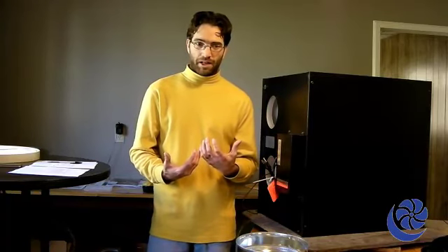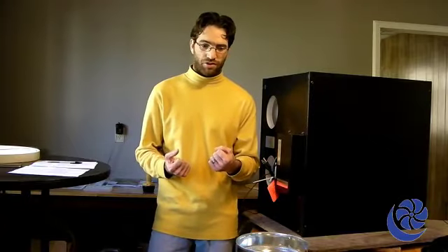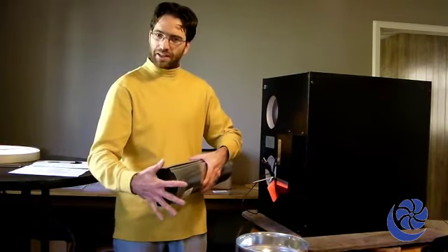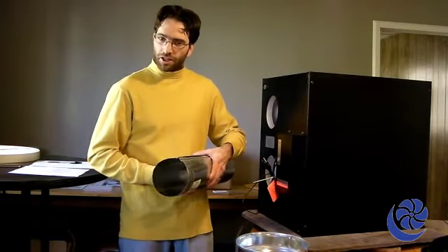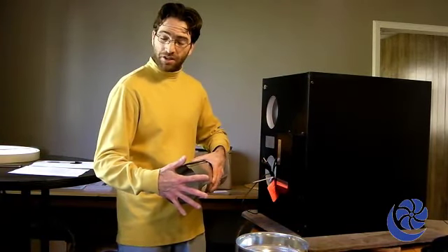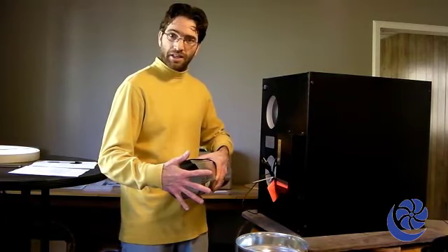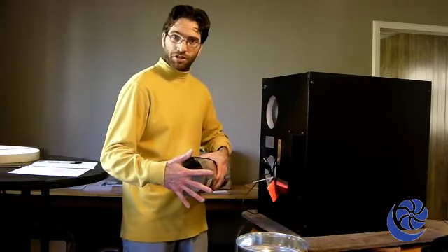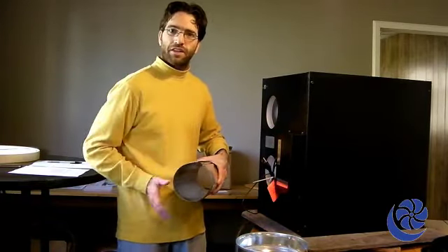Combine that with keeping in mind that we are delivering a very highly filtered airstream, meaning that we are pushing this air through a very dense filter, which also costs electrical money to force air through a filter. If I were forcing air through this duct without anything blocking it, and I were moving 100 cubic feet per minute through it, and then I decided to put a filter on the end of it and continue to move 100 CFM of air through it, you can see that with the filter, it most surely is going to cost me more electrical energy to push that same amount of air through a filter than if there was no filter.